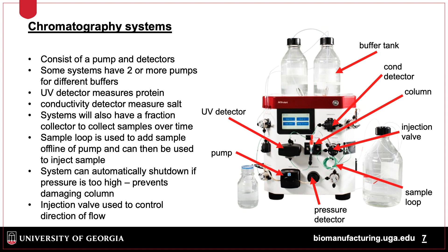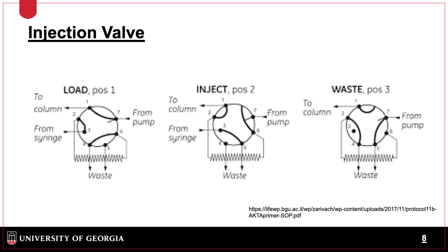One critical part of these systems is the injection valve. It usually has three settings: load, inject, and waste. The load setting means that the sample loop is out of the flow path and can be loaded. The valve can switch to inject so that the sample loop is in the flow path and material in the sample loop goes to the column. In the waste setting, buffer does not flow to the column or through the sample loop, but bypasses the system and goes directly to waste. This setting is useful for changing out buffers when different procedures are being run.